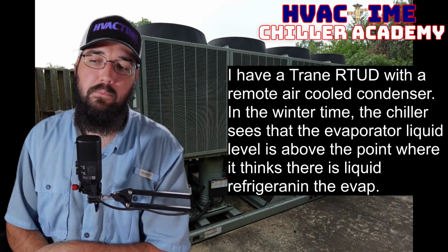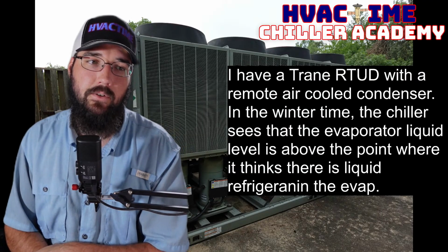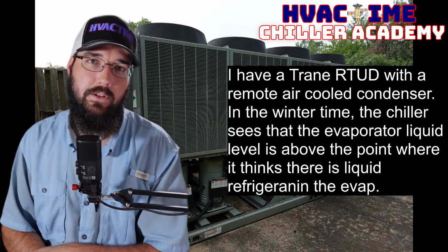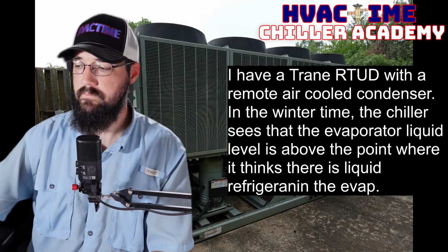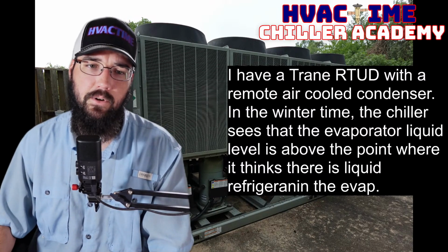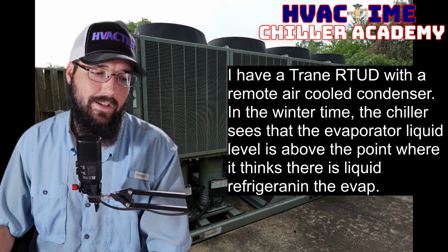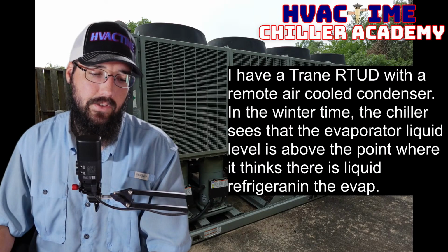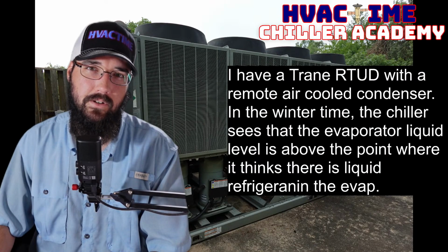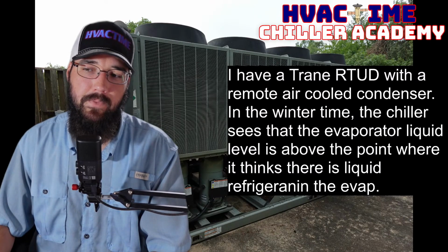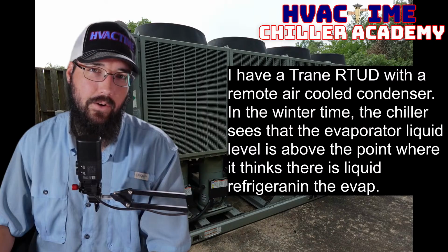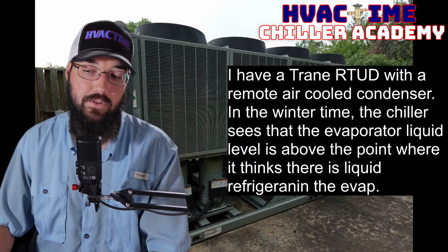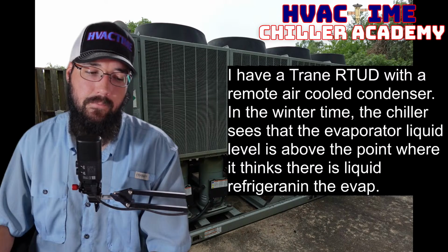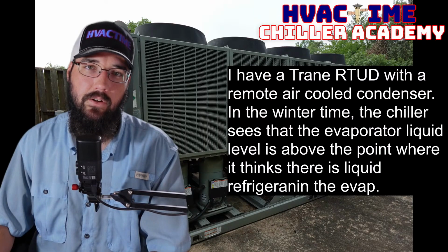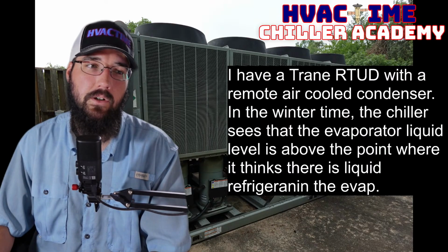Me being on site though, that would be the road. That's the road I'd be chasing down personally. Which, if I had to give a number, I would say I would want to maintain a head pressure of at least 70 to 75 saturation on the condenser, at least. And if I was pushing down to that or below, especially below, then that's when I'd really start thinking, okay, well then this is for sure part of that problem.